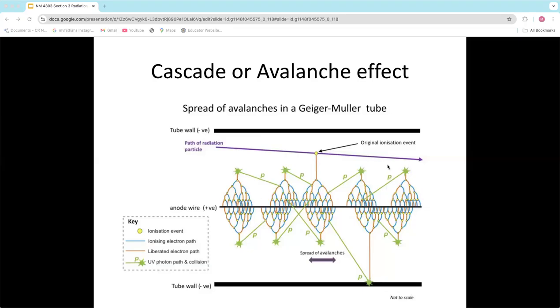Oh, and by the way, I should have said this at the beginning: a lot of the tubes are set up this way. What you have in the middle is your anode, right down the middle of the tube, almost like a wire. And then the walls of the tube essentially become your cathode. So everything's being pulled, causing more and more reactions. Essentially you get this avalanche effect where, because the voltage is so high, almost all the argon gas goes through this process of being ionized, okay?